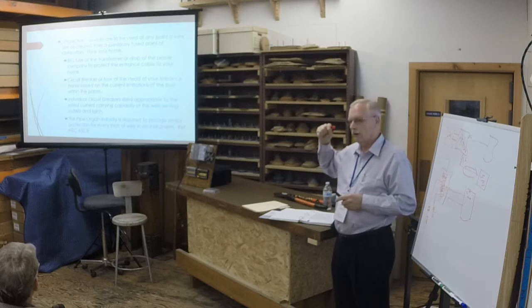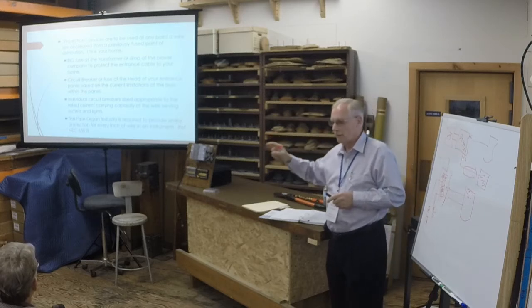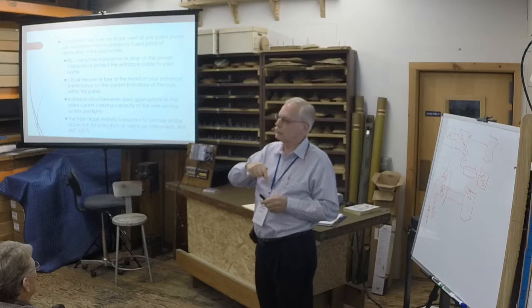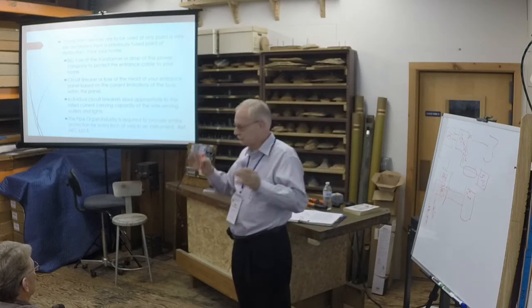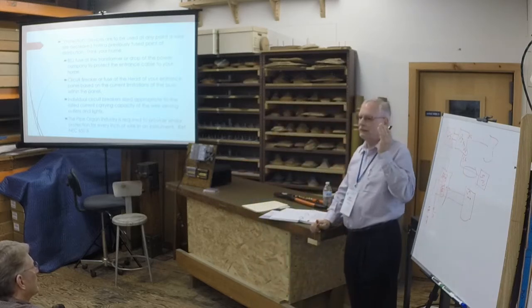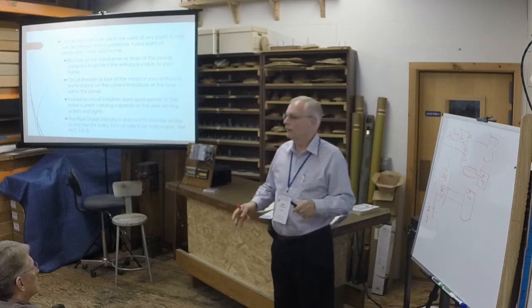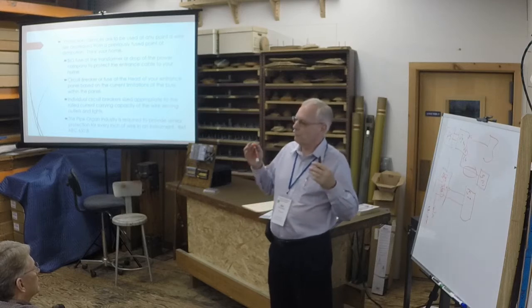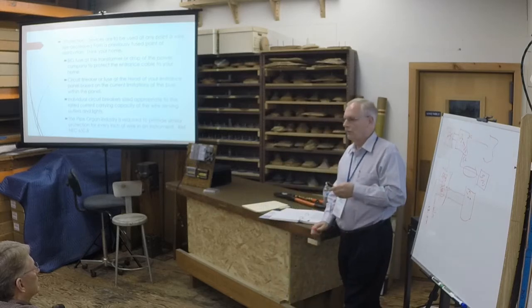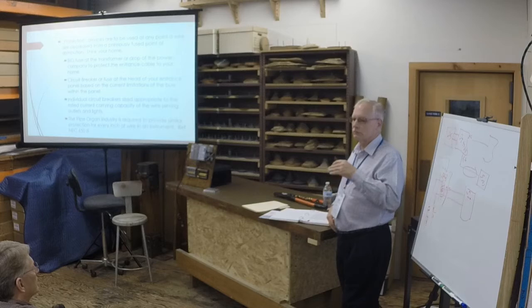At every single wire size, you need to calculate what that load is going to be on that wire. Now, you can put a larger wire on a smaller fuse, but you cannot put a larger fuse on a smaller wire. So just bear that in mind. If you want to put a piece of 10 gauge wire on a 5 amp fuse, feel free, okay? But you can't put a 40 amp fuse on a piece of 10 gauge wire. Okay. Again, use the charts. It'll get you real close to where you need to be. And that's what we just covered.